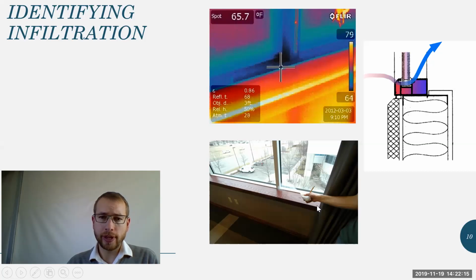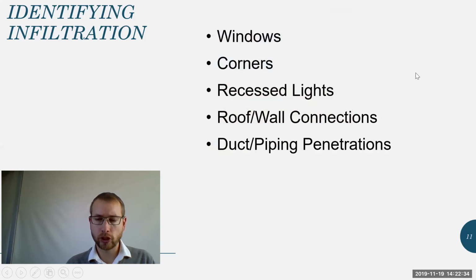All right, so just a couple of images here. It's really nice to be able to take pictures very close up, as I was saying, where you can see some of the air drifting through, and use a smoke pen as well to look at gaps around windows and the like. So where should you be pointing that camera or taking the smoke pen? Windows, right? The caulking around the edges, the seals can wear out over time. Corners of buildings, recessed lights are a big one. Roof to wall connections, as well as any penetration through the building: electrical conduits, your gas line coming in, even your HVAC ducts if they're not properly sealed around, right? Because you're bringing conditioned air down through the middle of the metal tube, but if you haven't added any insulation around the outside, you still might be getting some outdoor air in.